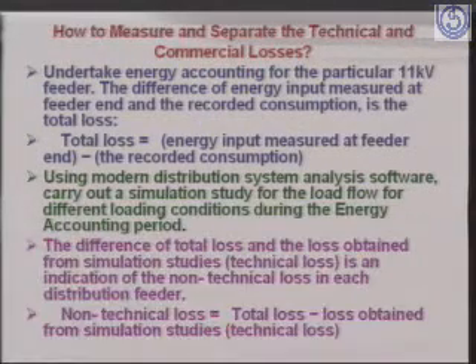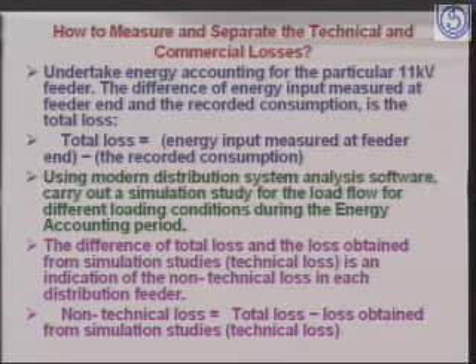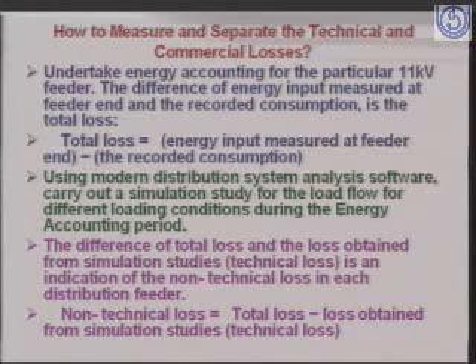Let's come back again to your subject, how to measure and separate the technical and commercial losses. One has to undertake energy accounting for a particular 11 kV feeder. The difference of energy input measured at the feeder and the recorded consumption is the total loss. That's what we discussed earlier. So total loss is energy input measured at feeder end minus the recorded consumption. Using modern distribution system analysis software, one can carry out a simulation study for the load flow for different loading conditions during the energy accounting period.